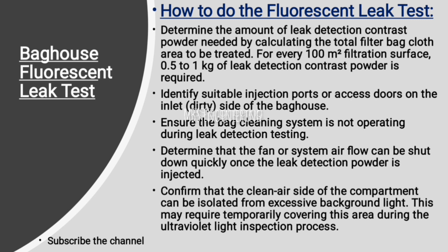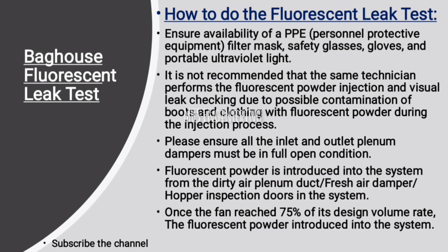Next step: determine that the fan or system airflow can be shut down quickly once the leak detection powder is injected. Next step: confirm that the clean air side of the compartment can be isolated from excessive background light — this may require temporarily covering this area during the ultraviolet light inspection process.